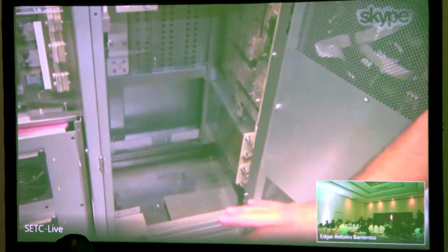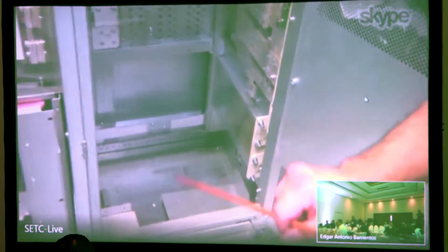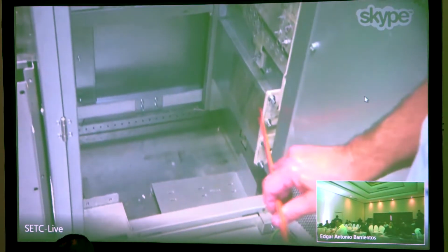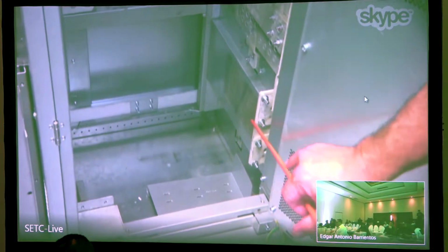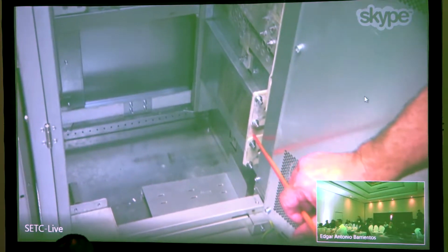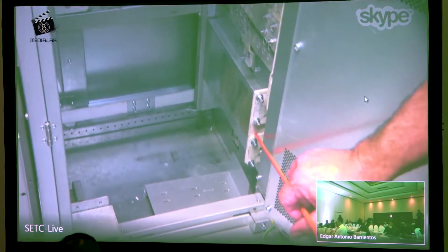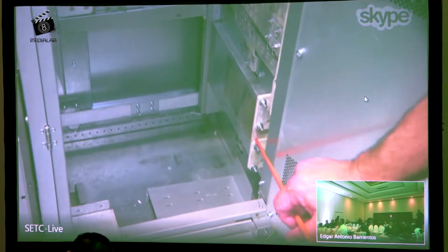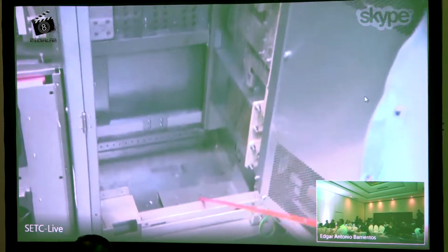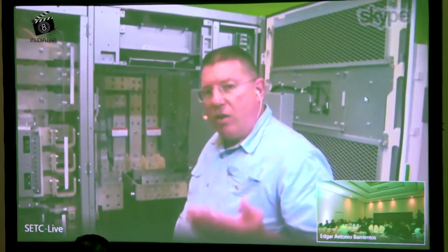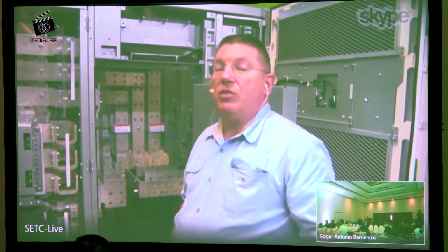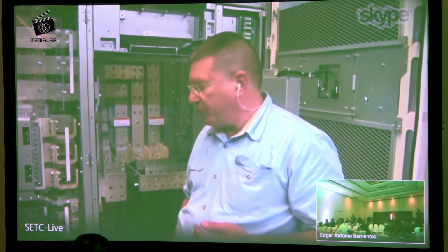Now, a couple other things we want to look at in here are top and bottom feed, and where our grounding is. So here's the ground bar. We can do a solidly grounded system or an HRG, high resistance ground. We're seeing more of that in the US. I'm not sure about Central America, but what we're seeing is older industrial facilities that already had a high resistance ground installed, and we're able to adapt to that.